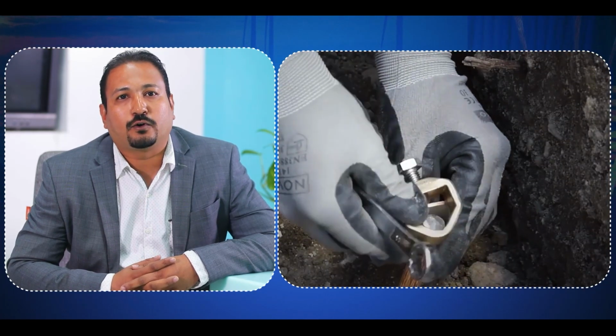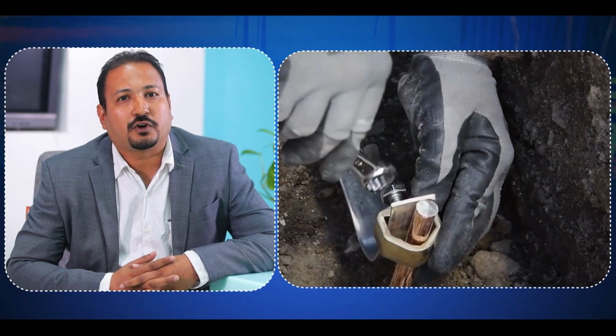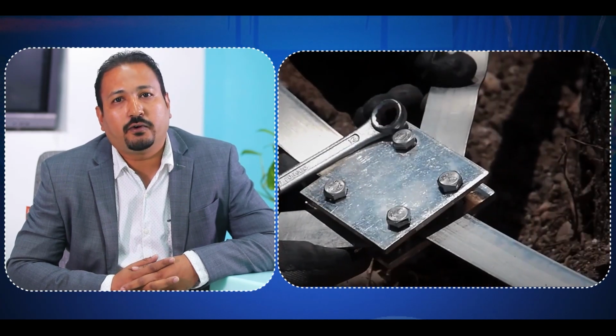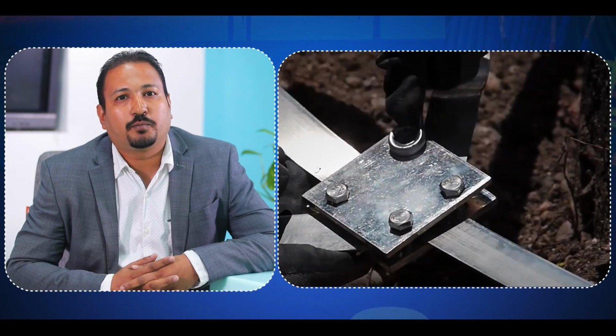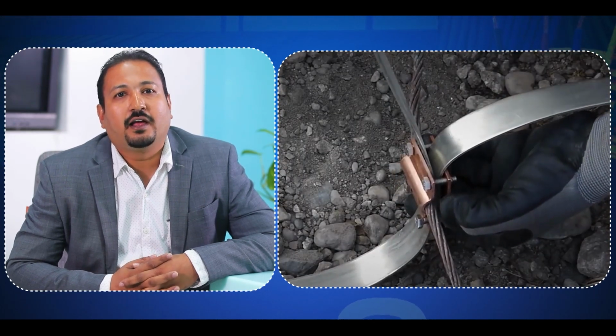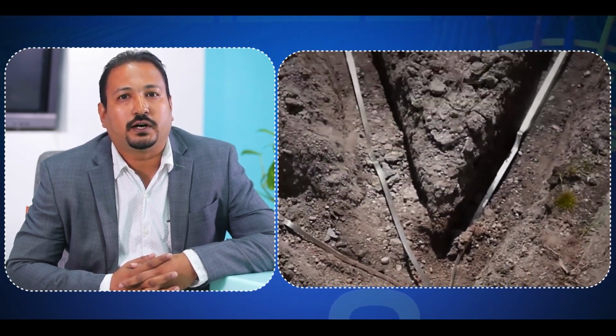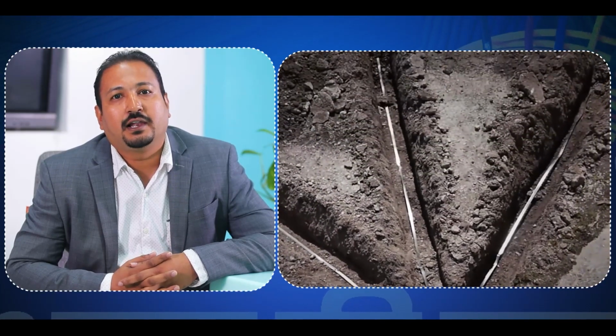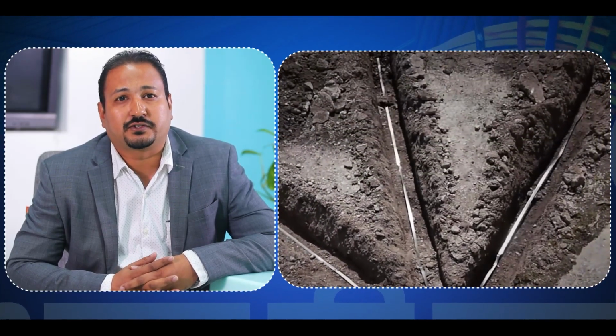Lightning looks fascinating to watch, but it is highly dangerous, because it carries a tremendous amount of energy, which not only damages the structure itself but also its occupants, contents and other systems. We do not have control over lightning, as we cannot stop or prevent it from happening. However, we can install a lightning protection system which safely diverts the lightning current to the earth, thereby protecting the structure, lives and various other important systems.